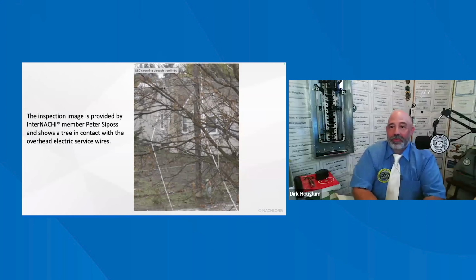Another common clearance problem is caused by trees and shrubs. This may interfere with the overhead supply. The inspector should take the time to eyeball this when they're doing their inspection, from the supply pole to the attached point of the structure. In the report, you should really report on all trees.